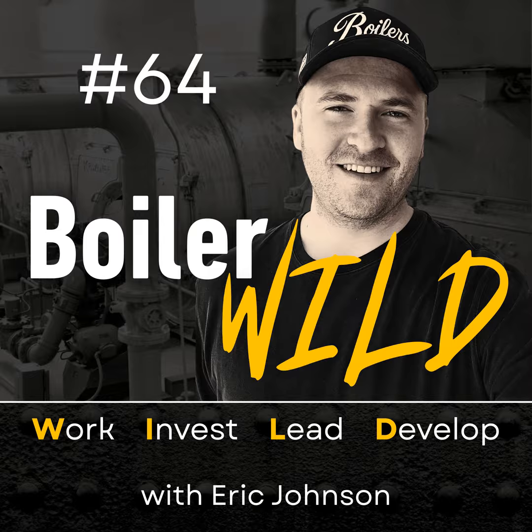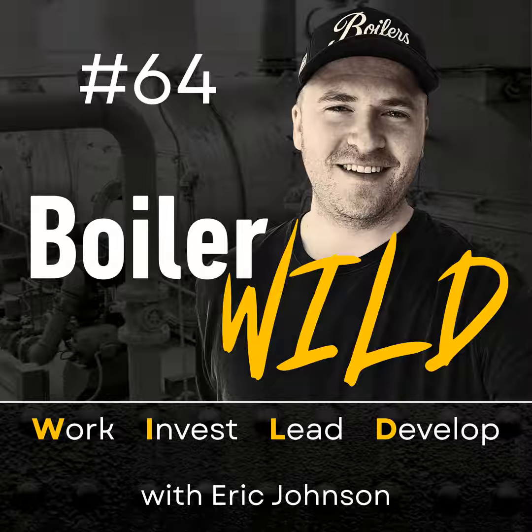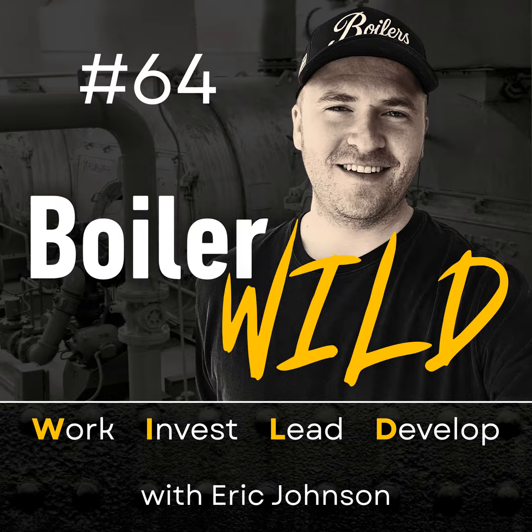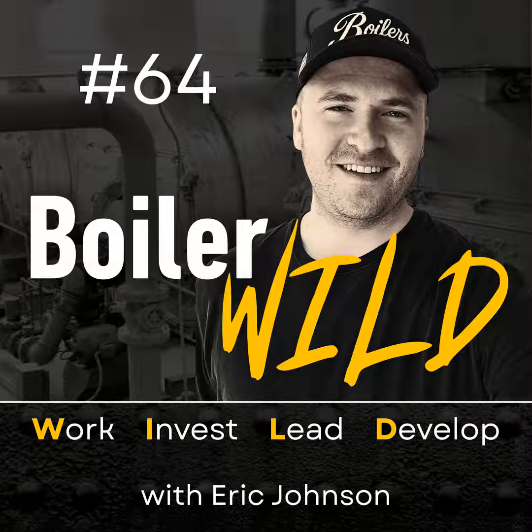So I checked at the input of the boiler, and I didn't have any 120. So then I went over to the wall and checked the 480. Didn't have any 480 and found out that the fuses had blown during the power outage and they just needed to replace some fuses. So they replaced the fuses and they're like, oh man, we've been working on this for hours. And they had all the covers off of all the electrical switches and they were trying to troubleshoot why that boiler wouldn't run. But they were just guessing. That's why troubleshooting, you always start with, do I actually have power to my equipment?